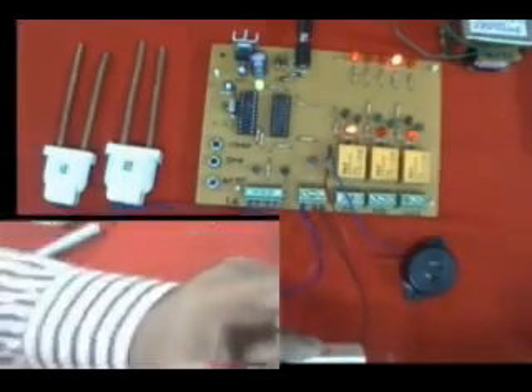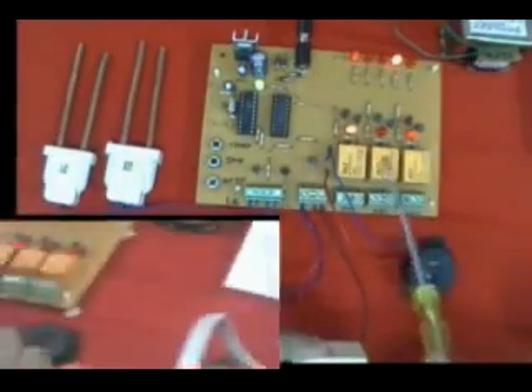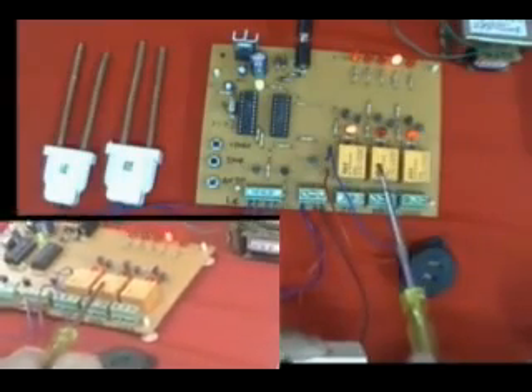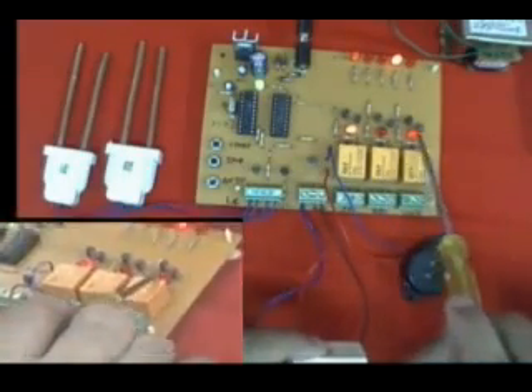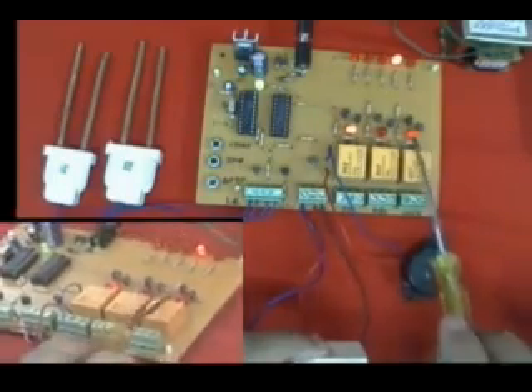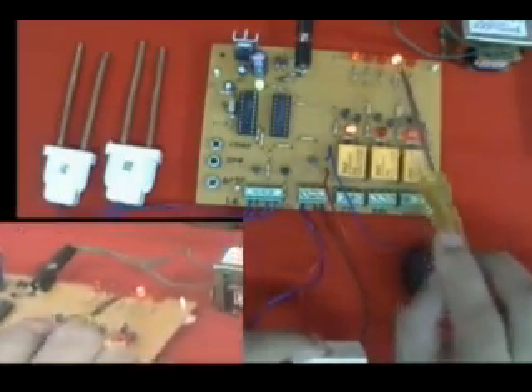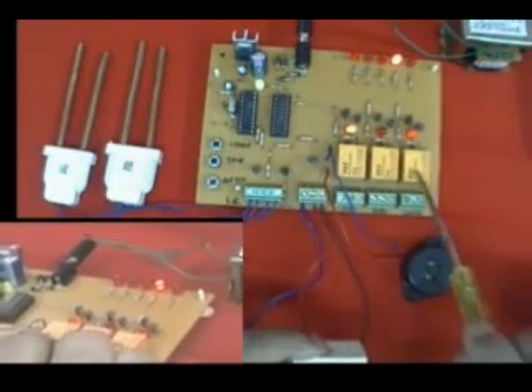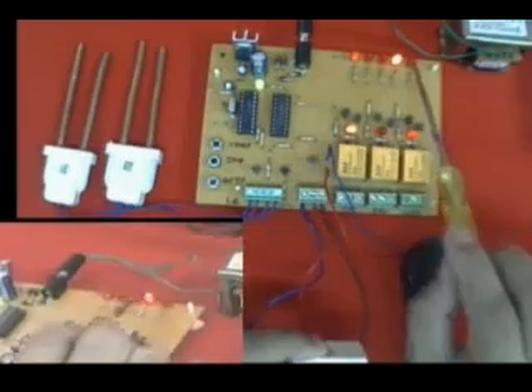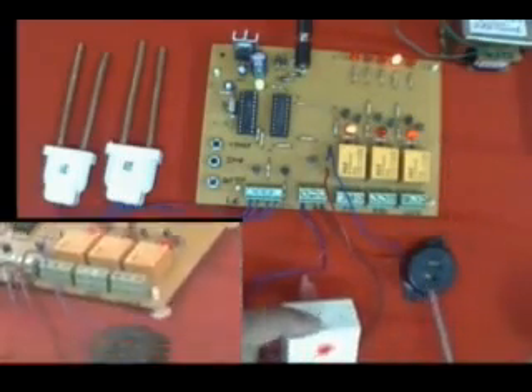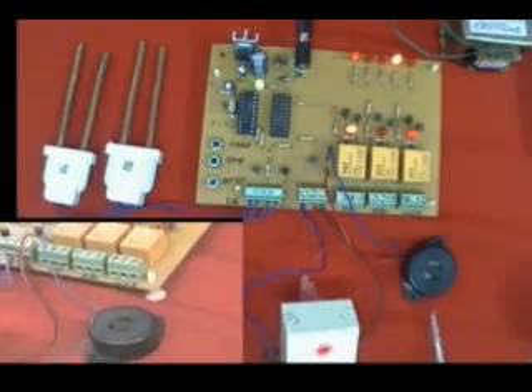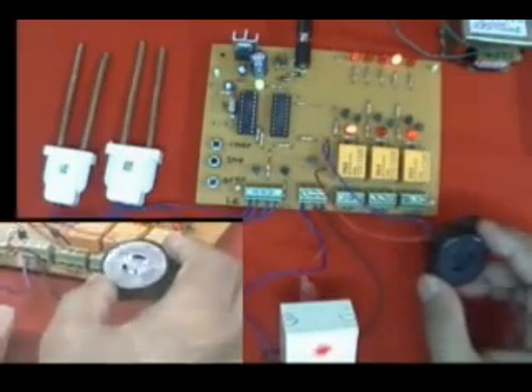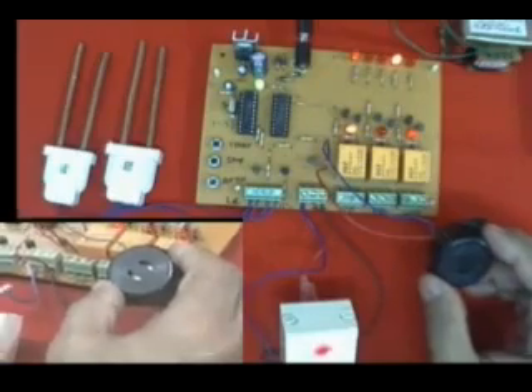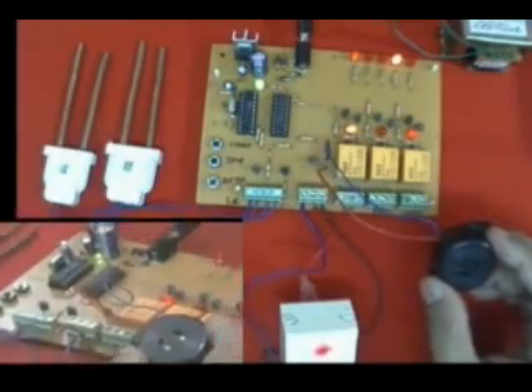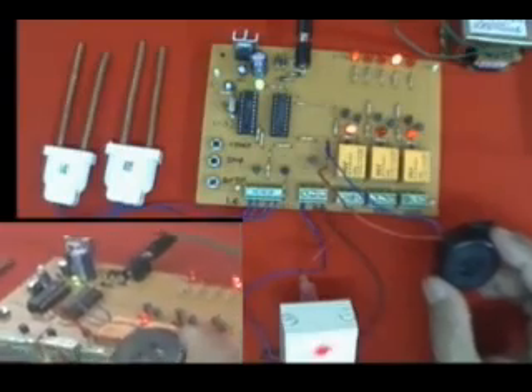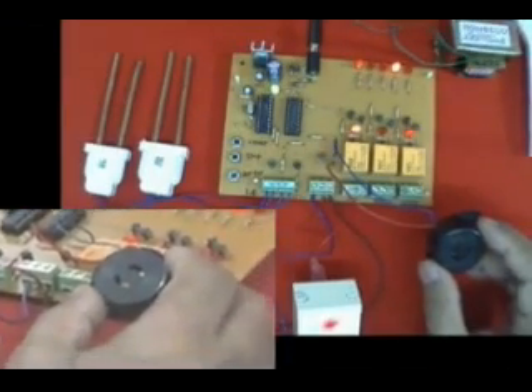and see what happens. This valve is shut, that is, the overboard valve is shut, and this oil valve has opened and the LED is glowing. This indicates that the waste oil valve is open and the overboard valve is shut. And this buzzer will stay on for 1 minute, so the siren will be there on the bridge so that the officer on watch can see physically from the bridge that no oil is being pumped out.